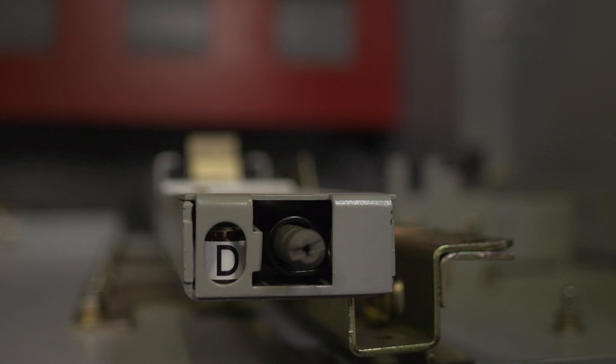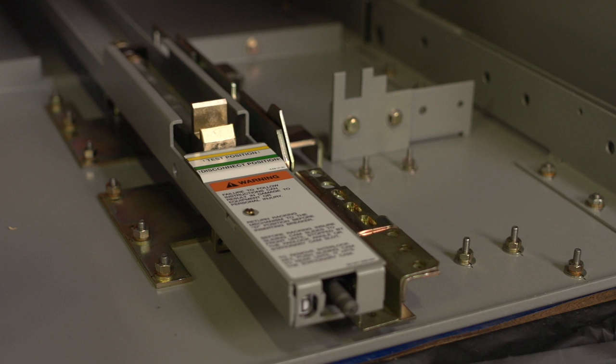Whether you manually or electrically rack the circuit breaker, the position indicator must be visible through the door. These yellow and green bars line up with the front of the circuit breaker. As the circuit breaker is racked, this block connects with the circuit breaker and moves in and out of the cell.